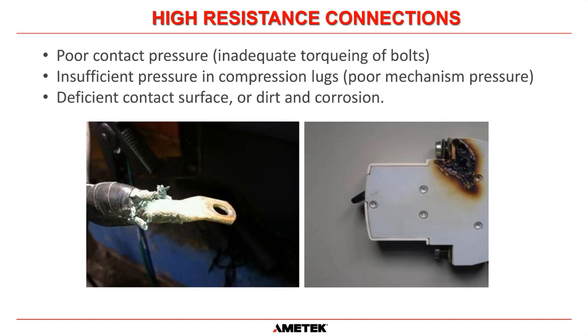And this picture on the right-hand side is a perfect example of what either a loose connection or a high resistance connection can do. There is going to be a voltage drop associated with that. And when there's current flowing through voltage, there is power. And that power is going to be dissipated in heat. And you can see how much heat was created here.